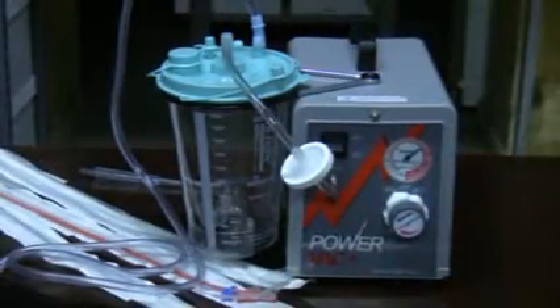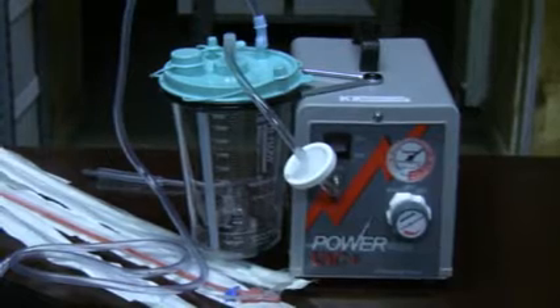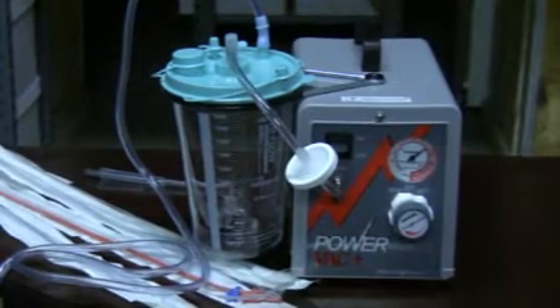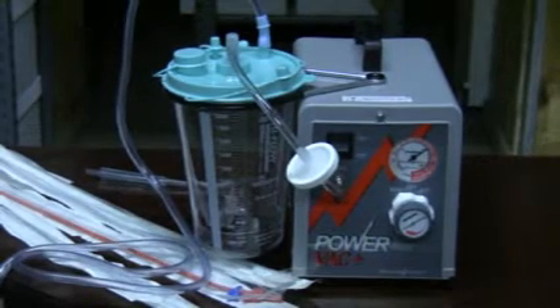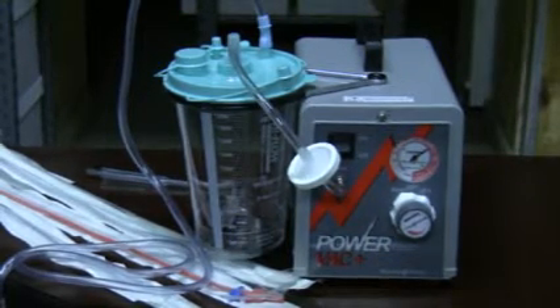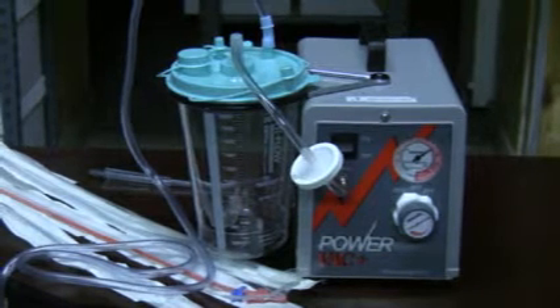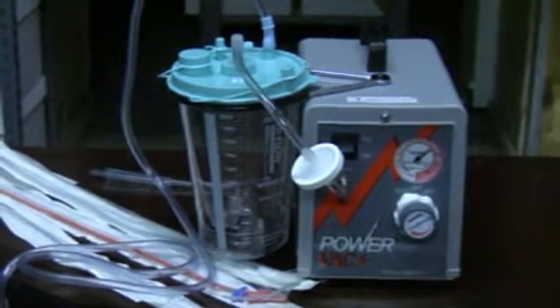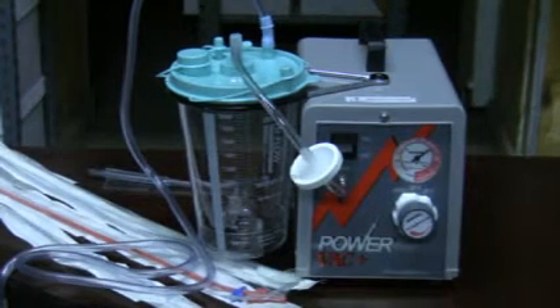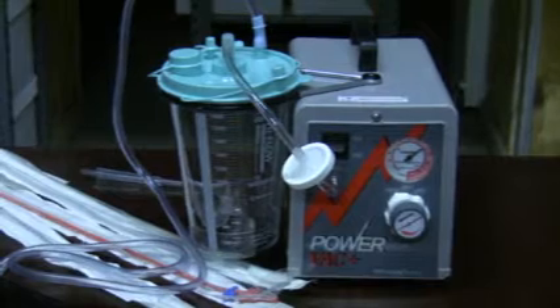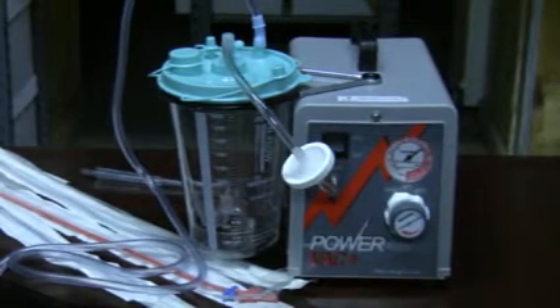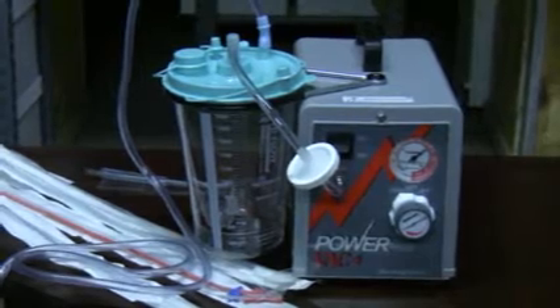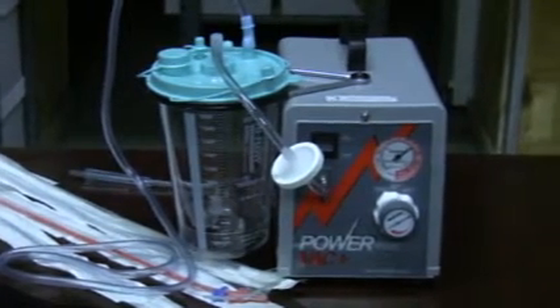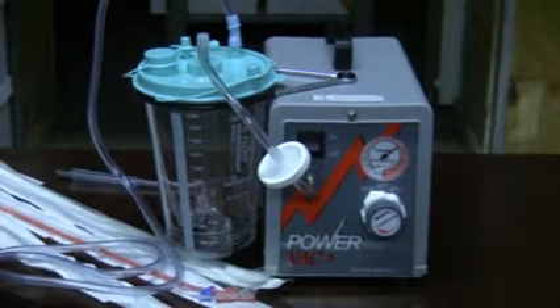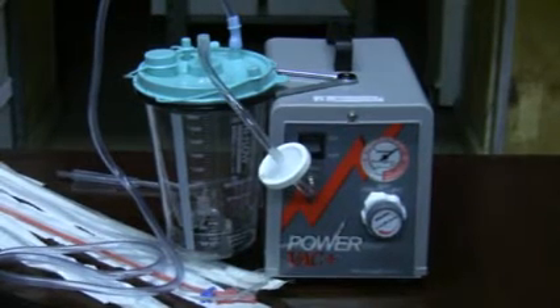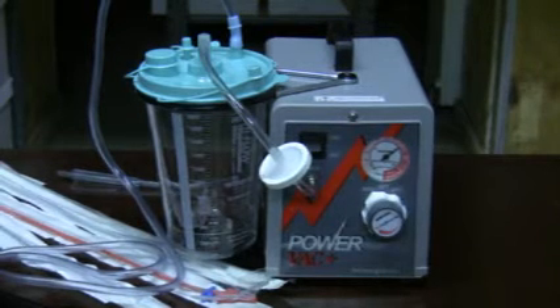If there is no power present with your intermittent suction machine, we previously stated you should check your power cord at the outlet, check your power cord at the rear of the machine, as well as check your fuses located underneath the receptacle where the power cord plugs into the rear of your intermittent suction machine. If the power is present in the outlet, your fuses are okay, and all connections are firmly secured, your intermittent suction machine thermal limit may have been reached and may have been powered off in order to reset and protect your intermittent suction machine from further damage.